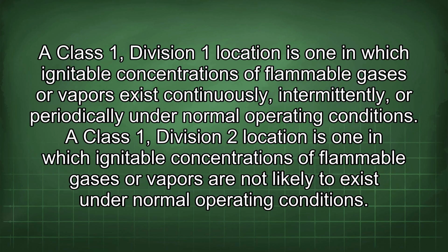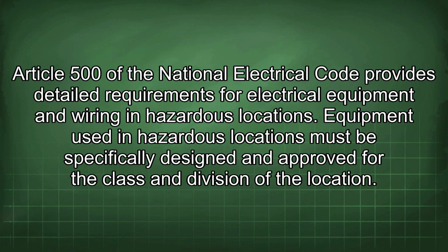A Class 1, Division 2 location is one in which ignitable concentrations of flammable gases or vapors are not likely to exist under normal operating conditions. Article 500 of the National Electrical Code provides detailed requirements for electrical equipment and wiring in hazardous locations. Equipment used in hazardous locations must be specifically designed and approved for the class and division of the location.